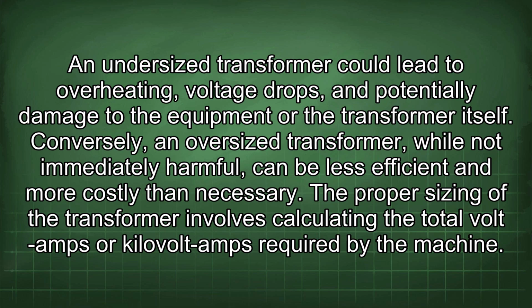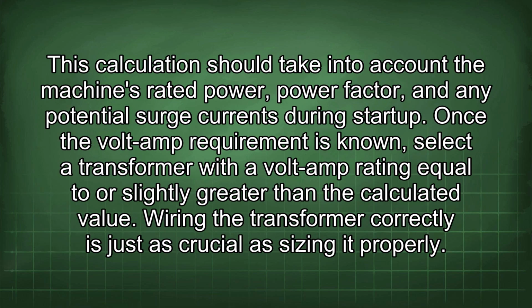The proper sizing of the transformer involves calculating the total volt-amps or kilovolt-amps required by the machine. This calculation should take into account the machine's rated power, power factor, and any potential surge currents during startup. Once the volt-amp requirement is known, select a transformer with a volt-amp rating equal to or slightly greater than the calculated value. Wiring the transformer correctly is just as crucial as sizing it properly.